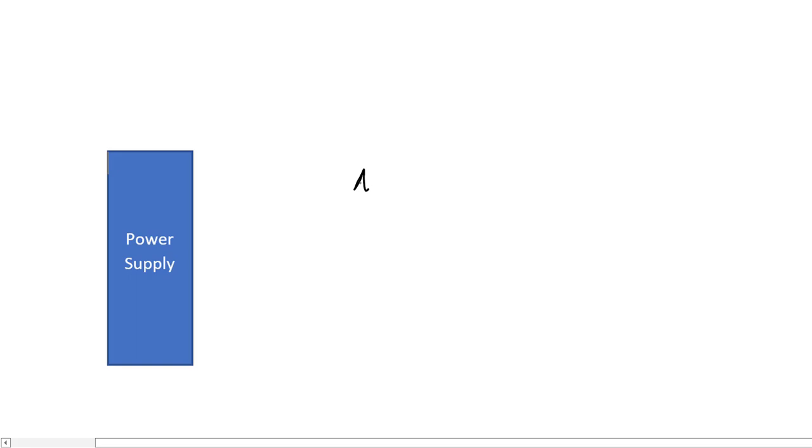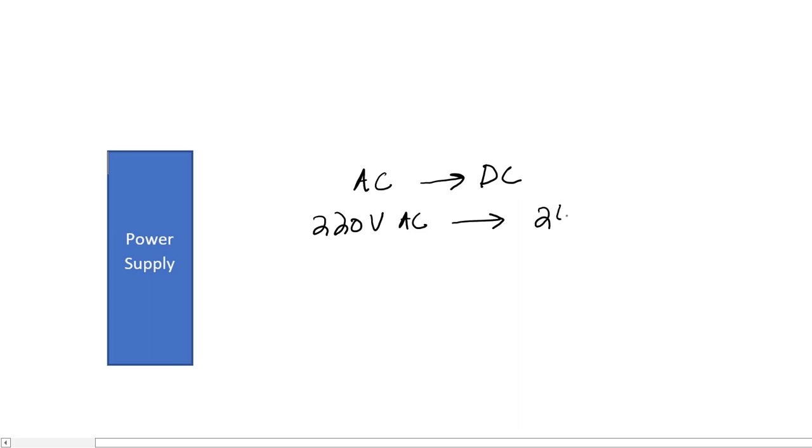First let's talk about the power supply module. The purpose of the power supply module in a PLC is to convert AC voltage to DC voltage. Normally a PLC CPU requires DC voltage for its operation. Normally we provide 220 volt AC voltage to a power supply, and the power supply converts that AC voltage to 24 volt DC, and this 24 volt DC is then supplied to the CPU.